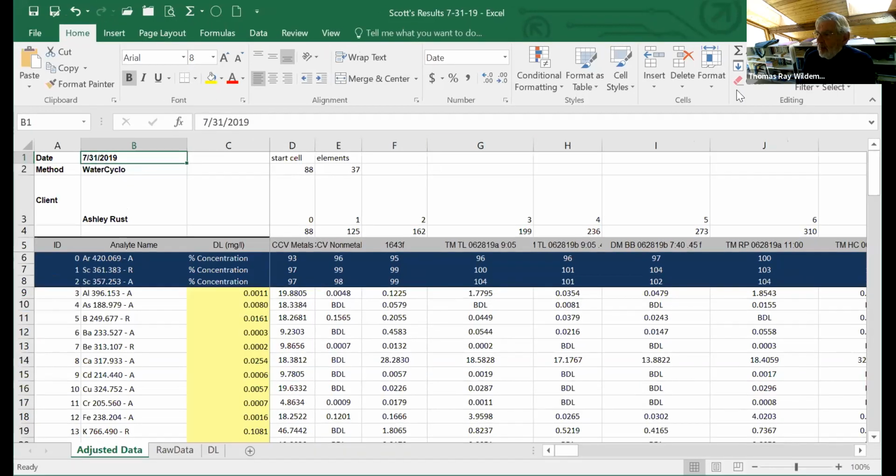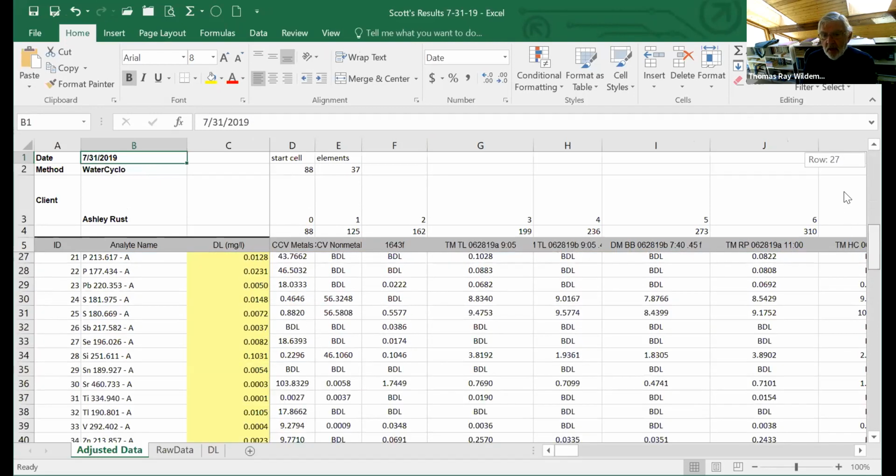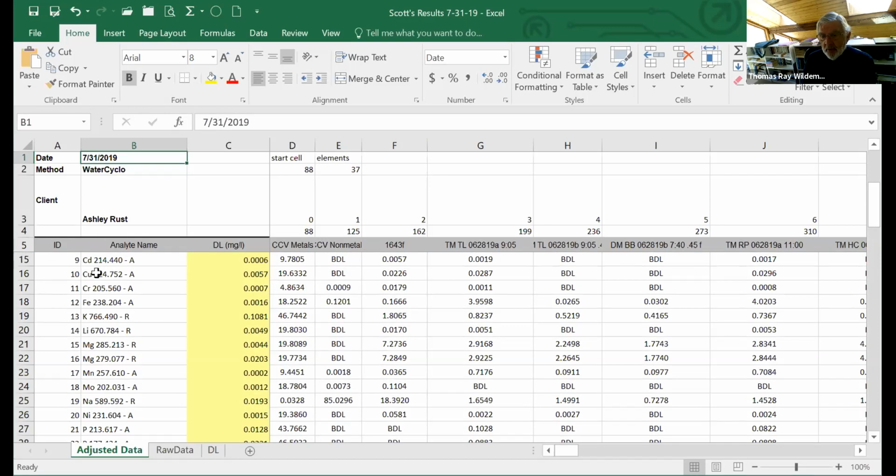So I'm going to go back, zoom in again here, like about there, okay, and explain what's going on. This would be the typical computer output. Here you have the elements that we have analyzed, and I think there's around 33 or 31 elements here, as you see. This is the emission line that we use. There is the sodium, that 589 nanometer line, as you see here. You don't need that in your results. We just have it because in some cases, like magnesium, we have two lines in here just in case. Okay, so that's the first column here.